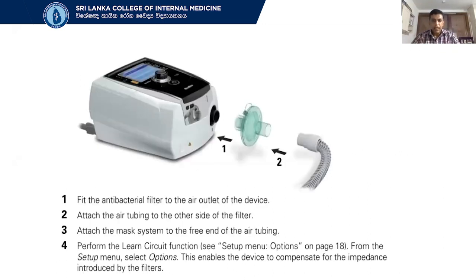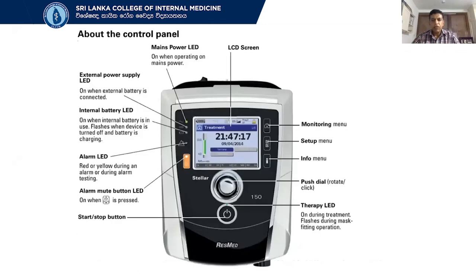Now, this is a ResMed Stellar machine that most of us are very familiar with. You have the humidifier; we remove the humidifier, put in a viral filter, and then connect the patient there, preferably with a non-vented mask. Now, you need to be familiar. This is the ResMed Stellar 150 machine, but most of us have the 100 machine, and it's more or less the same. So you need to know these machines, and you need to know how to adjust them when you fall into trouble, right? So just read up on this. It's very simple, but you need to familiarize yourself with the machine that you are handling.